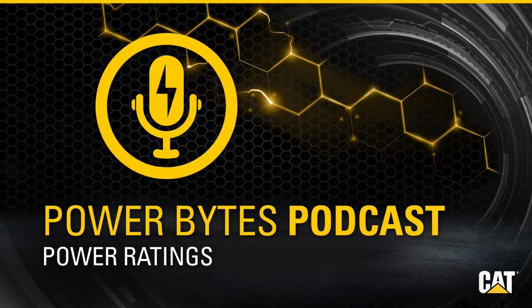Yeah, let's start out with the continuous power, or COP as it's referenced in the standard. Continuous power applications are typically those which have a consistent electrical load, and they have 100% load factor allowed for unlimited hours. Normally you're going to think about these in applications like a mine, where the load is fairly consistent and it runs 24 hours a day, so you're always getting the same amount of power. The generator is able to remain fairly consistent.